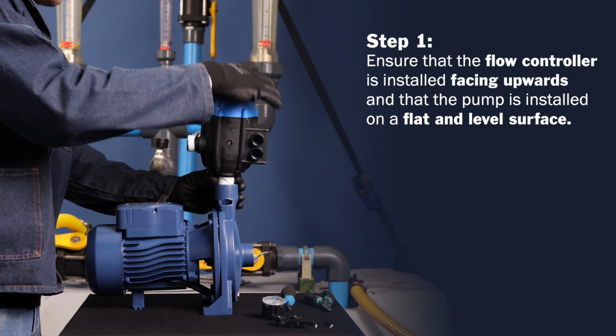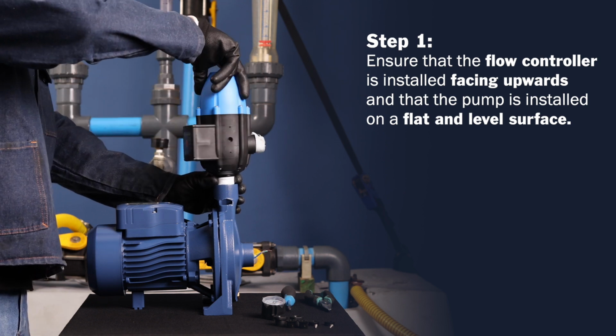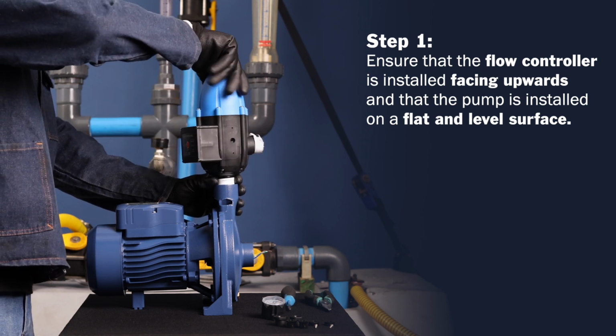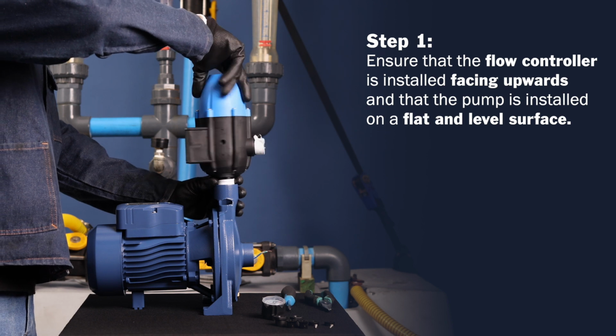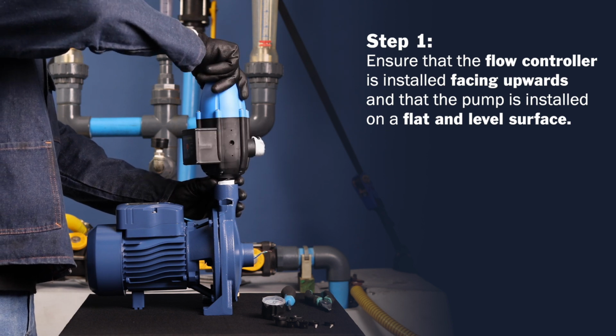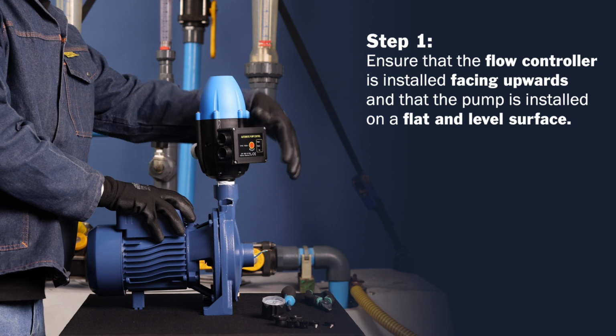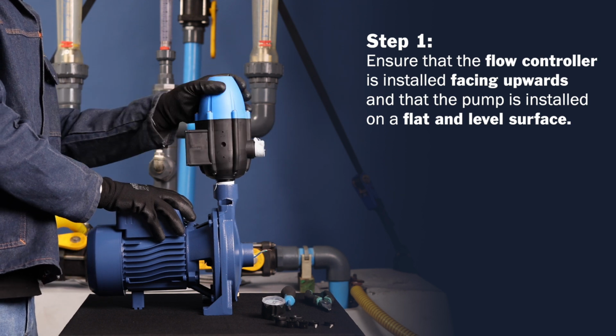Step 1. It is of utmost importance to install the flow controller with the correct side facing upwards, because the working of the flow controller is influenced by gravity. The pump's footpiece must always be on a flat and level surface to achieve the desired results.